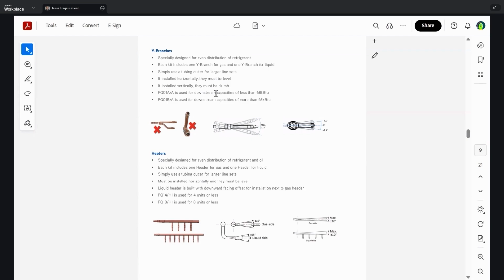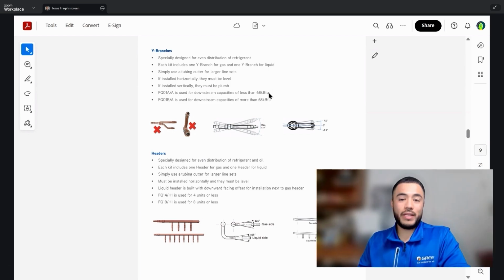FQ01AA is used for downstream capacities of less than 68,000 BTUs. FQ01BA is used for downstream capacities of more than 68,000 BTUs. So a good way to look at this is typically you'll see this FQ01AA used for all the MultiPRO single phase equipment. FQ01BA is used mainly for commercial. Typically that's where you'll see it, in commercial applications, is when this will come into effect.